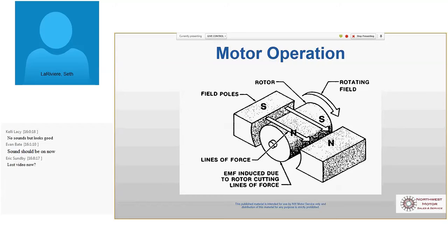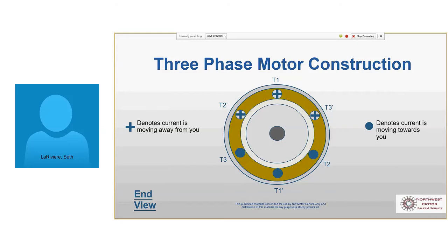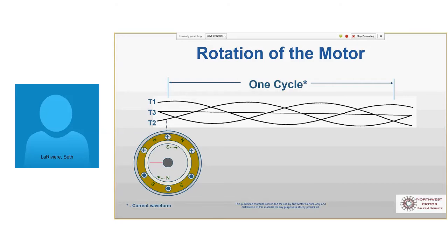This basically says whenever you have a piece of steel or iron between two magnets, it cuts those lines of flux, which is shown here, and then you've got magnetism induced into the rotor. Again, this is the positive and the negative, the two poles in pairs. This is basically what's happening in one cycle of a 60 cycle machine. So we start off in the first position. We've got the first pole here, north, positive and negative, shaft position there.